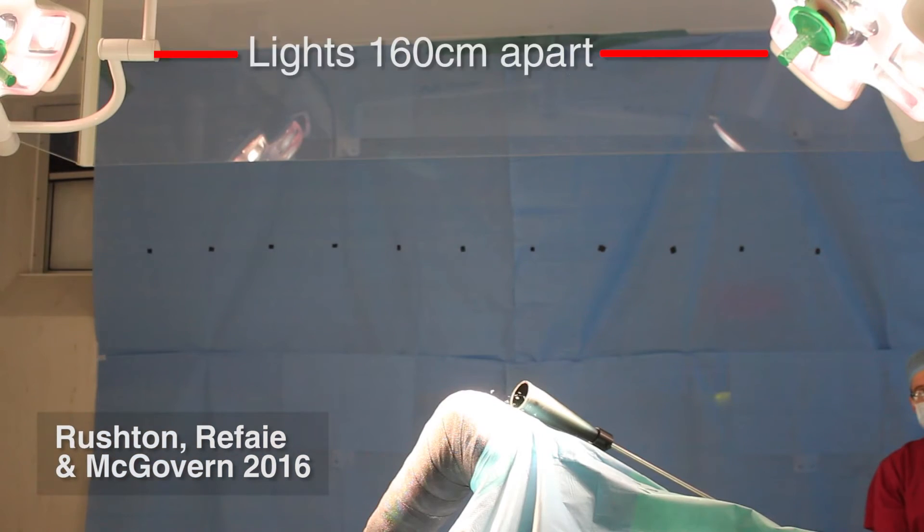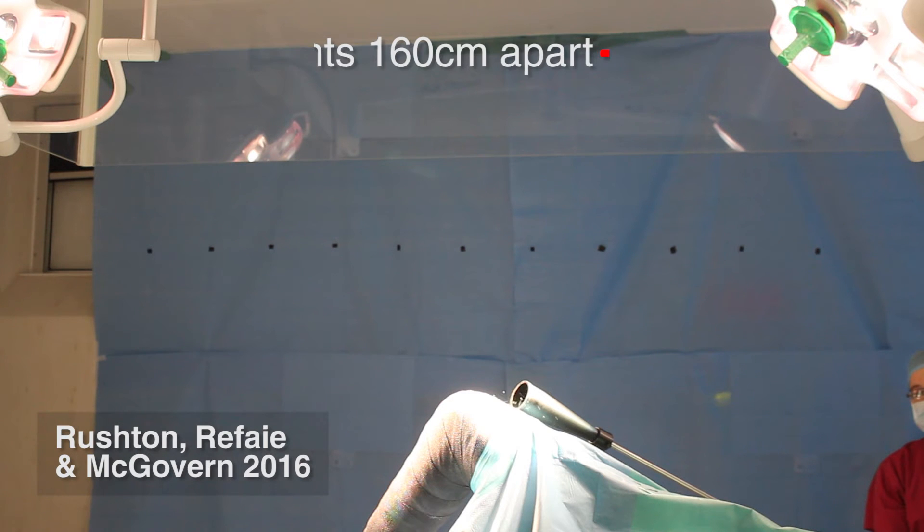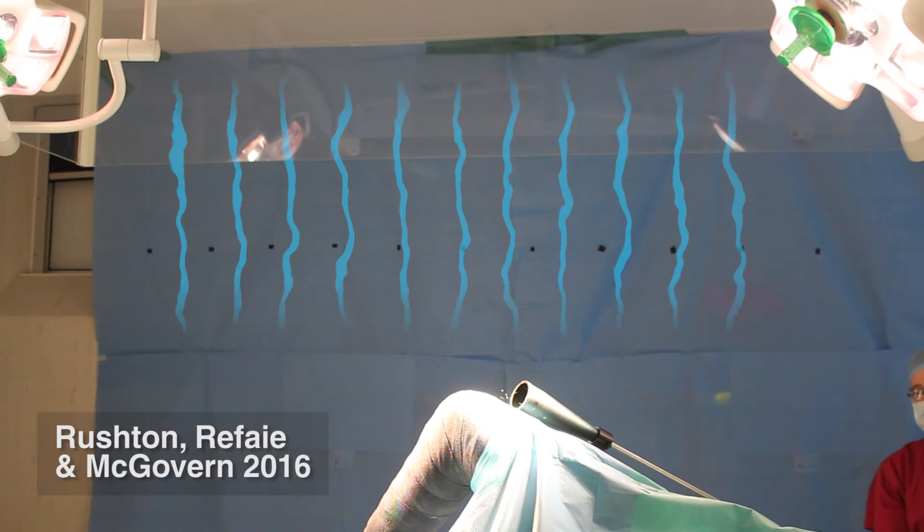This is how it should look. We're using the same bubble generator in the same room and we've made no changes to the setup of the room. Laminar flow is working — it's clearing the bubbles away before they have a chance to accumulate and circulate.